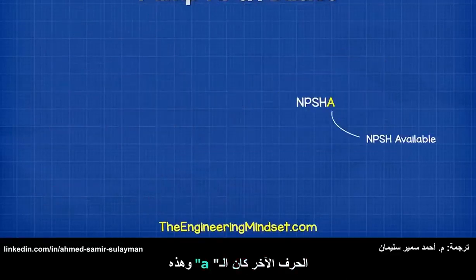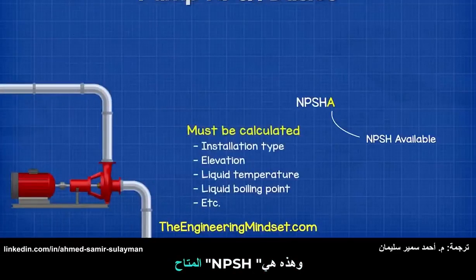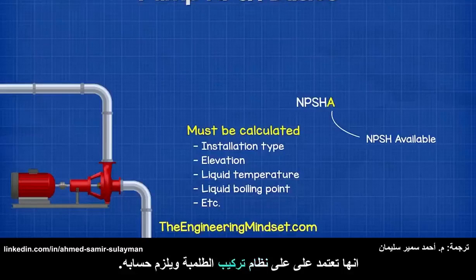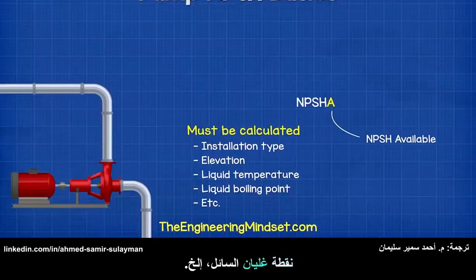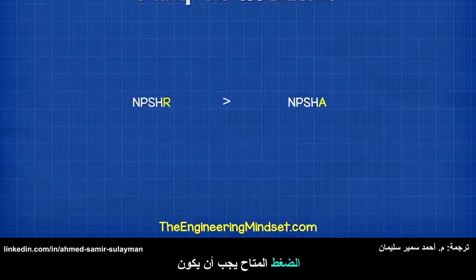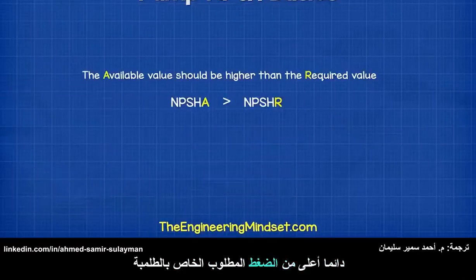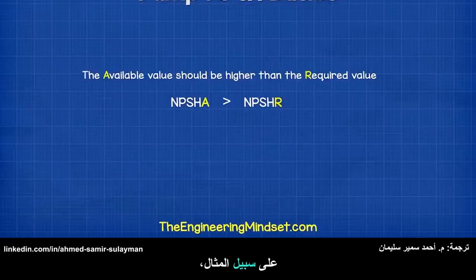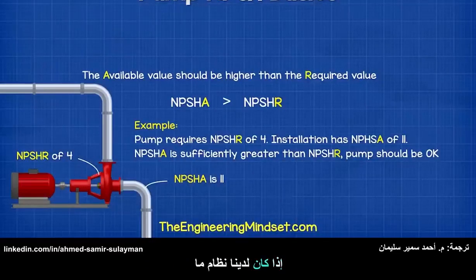The other letter was the A, and this is the NPSH available. This depends on the installation of the pump and needs to be calculated. It considers things such as installation type and elevation, liquid temperature, liquid boiling point, etc. The available pressure should always be higher than the required value. For example, if we have an installation and we calculate the NPSHA as 11, but the pump requires an NPSHR of 4, then the pump should be okay.